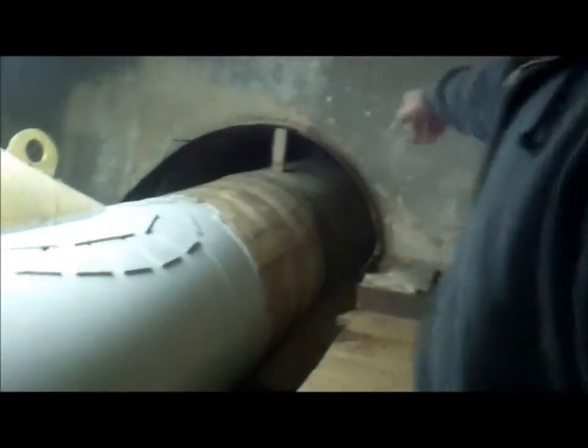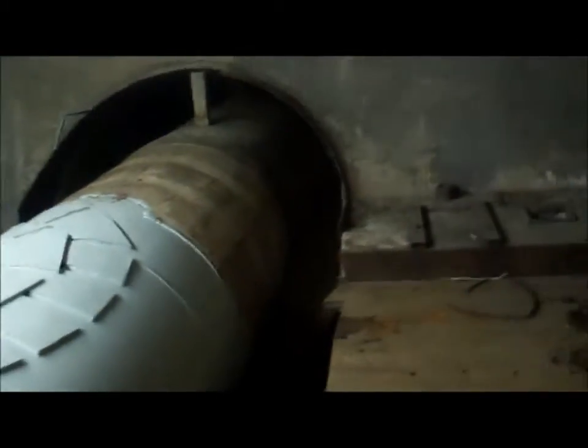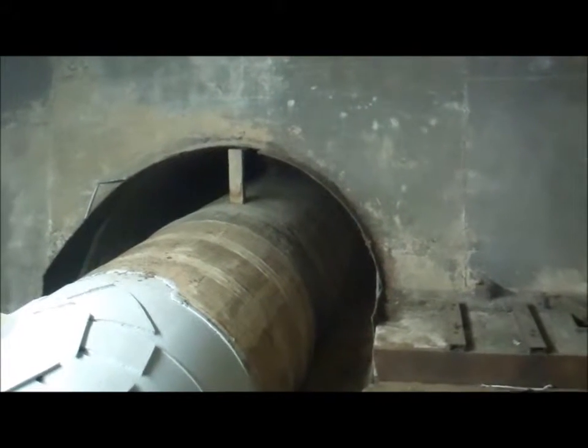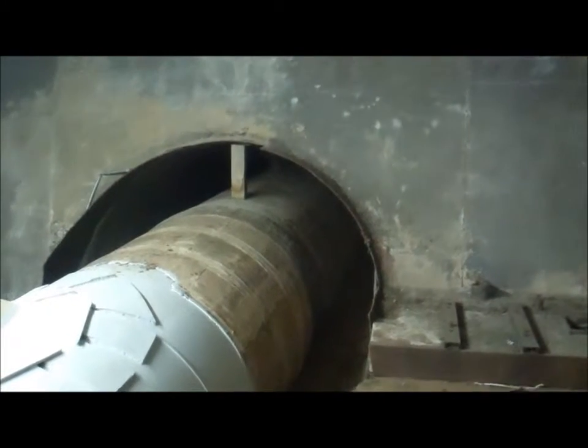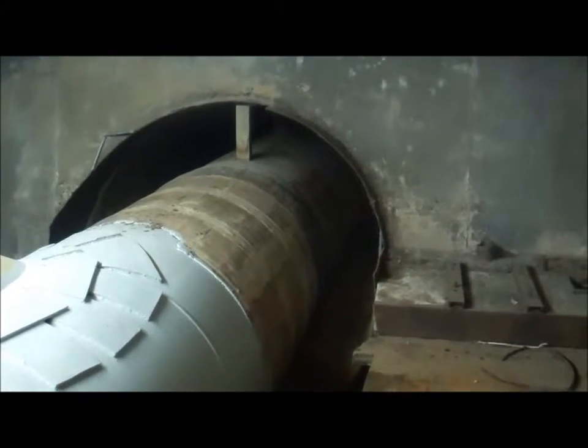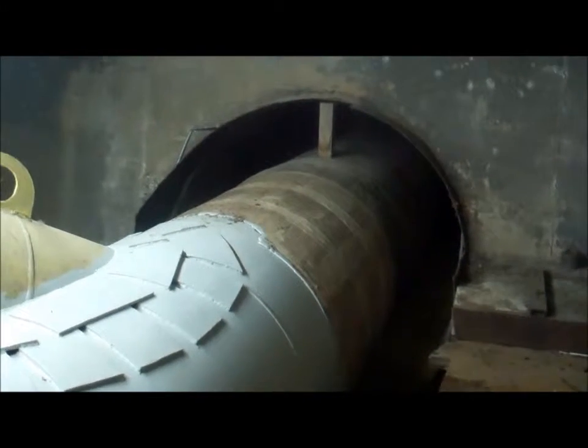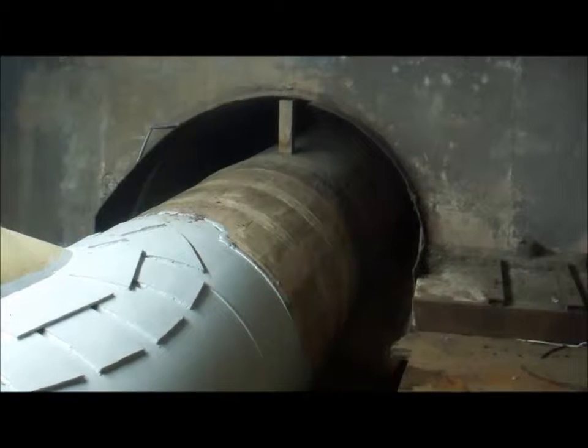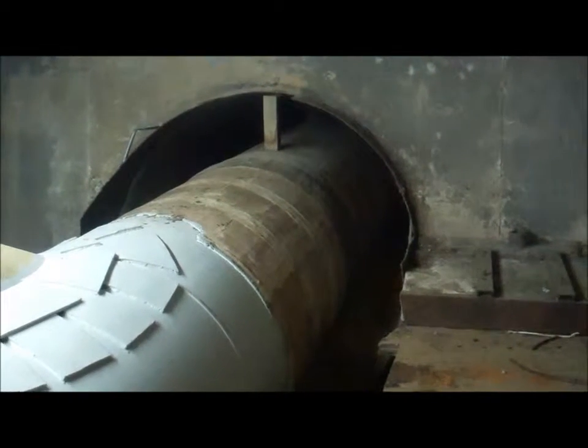That big pipe right there is the original diameter of the pipe that goes all the way up to the dam. Outside this building, it's reduced because they didn't want to bring that much water in an ancient pipe into this building, because if you did have a rupture, you'd fill this building up with water in seconds. So it splits off and goes three ways before it's reduced in diameter.